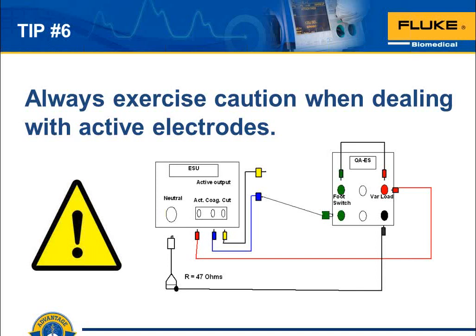We really don't want any of that kind of connection at all. And you don't have to have it that way. You really can these days make the connections without having any of that showing, with no exposed metal that's going to be conductive or heat producing or anything like that. So I've shown you here in this slide a simple illustration that was created by one of our customers in Microsoft Paint, of all things, to show how to hook up, for example, an ESU analyzer to the ESU itself, and in order to get the testing right.